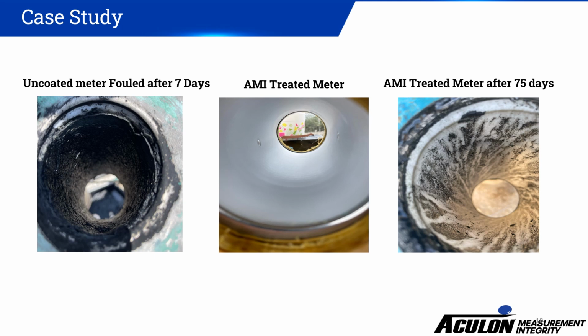Here are just a few examples of untreated and treated meters that have been in service. On the left, you can see a meter that's fouled after just approximately 7 days. This meter has both organic and oil residue buildup inside of it, coating both the PTFE liner and the electrodes. Here in the center is an example of a meter that has been pulled out, cleaned, and then treated with the AMI treatment. On the right, you can see a meter that has been in service for about 75 days. Notably, you can see beading on your PTFE liner, but most important, your electrodes are still clean and able to read accurately as flow flows through it.